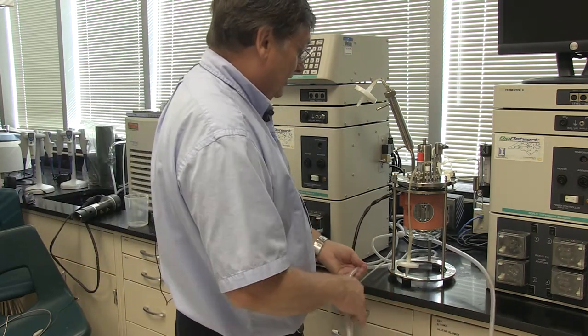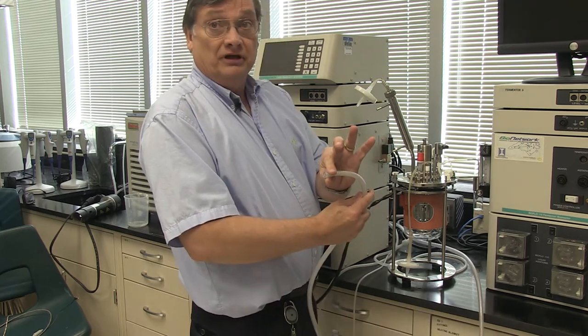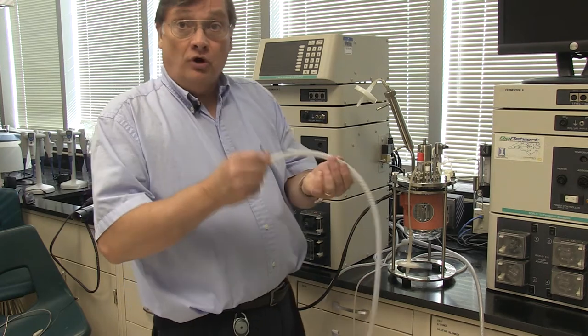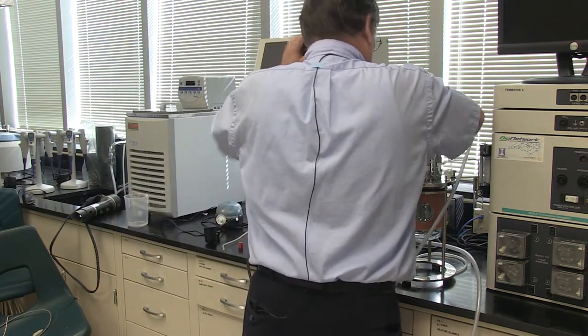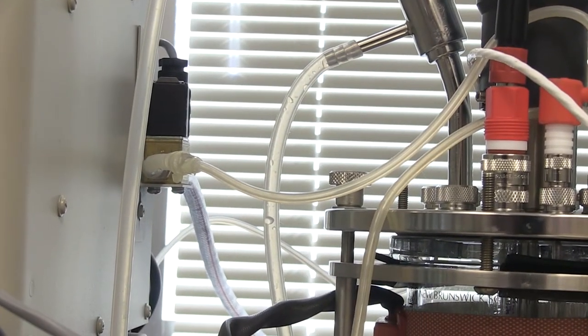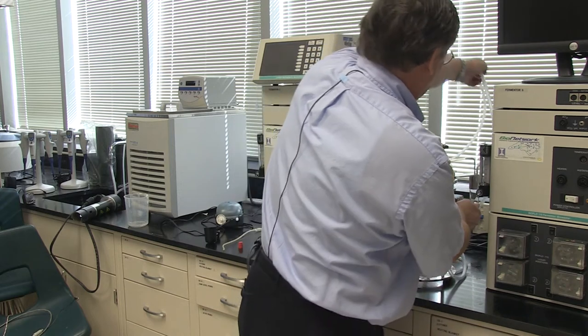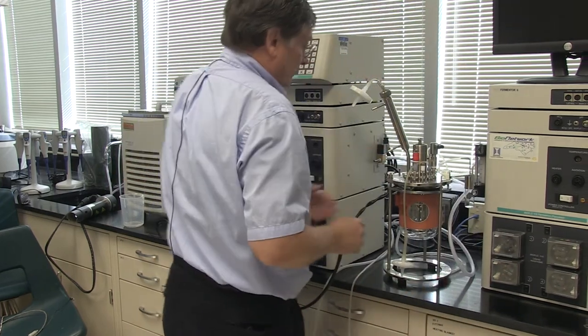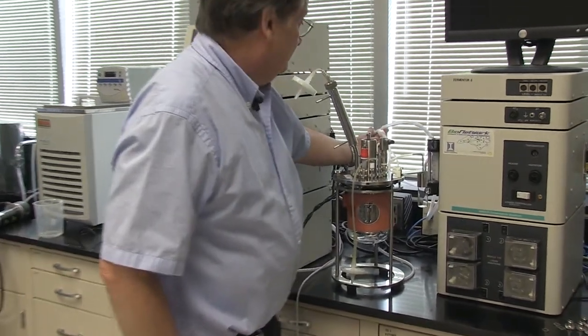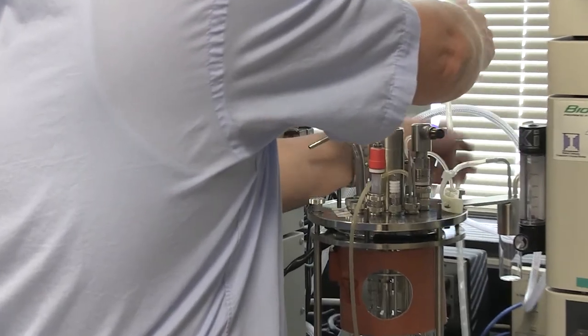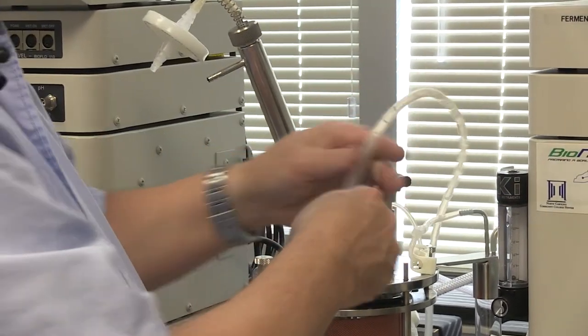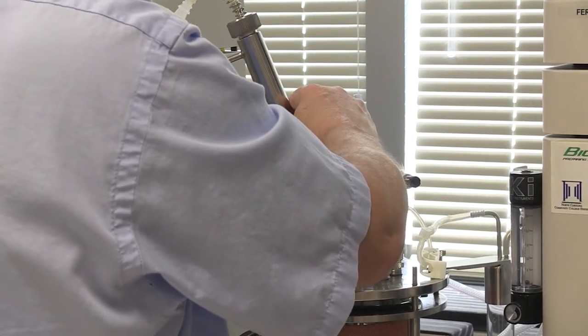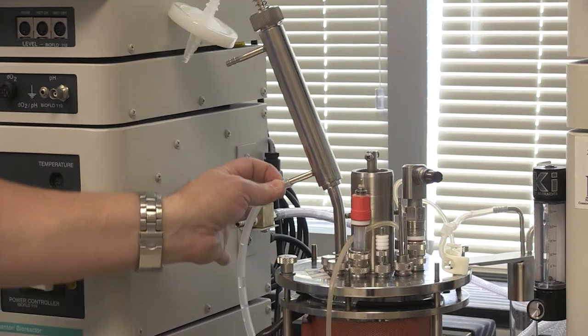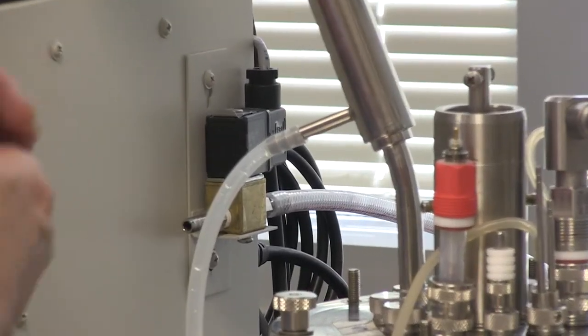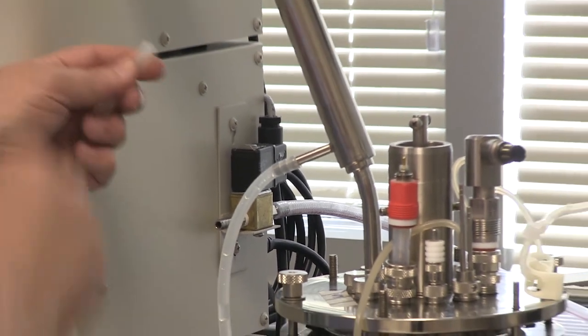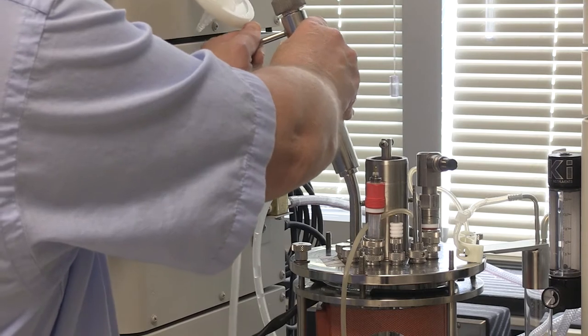Right. So we have this braided tubing that comes in from the faucet or your chilled water source, and it's going to hook to the back of the solenoid. So let me get it out of the way now. Great. Now, coming off of it, if you can see through here, there's a T. And this smaller tubing that's not braided is going to feed to the bottom of the condenser. And then we have another drain line that's going to go back to the sink or to the recirculating unit, and it goes to the top.